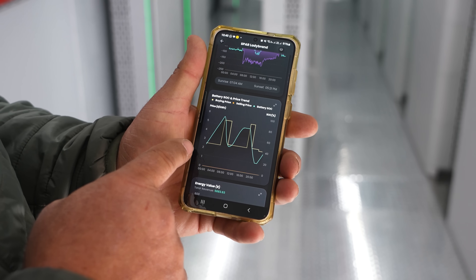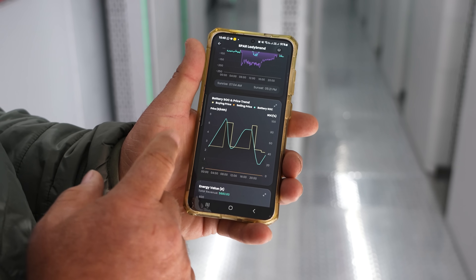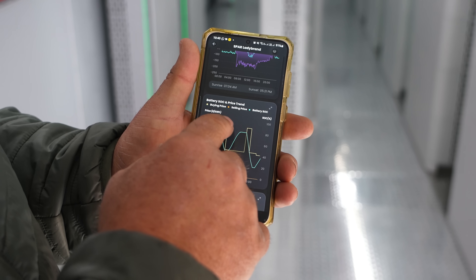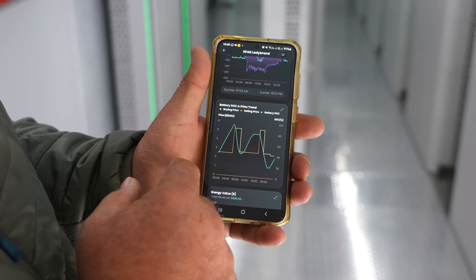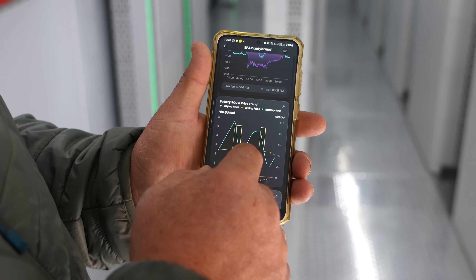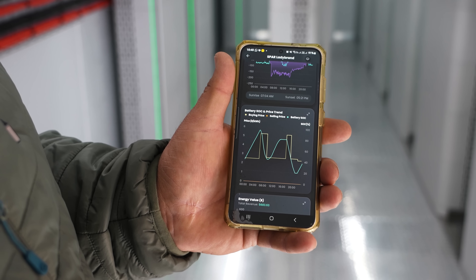What you can see here is the battery state-of-charge profile. We charge the batteries up in winter during the night after 10 o'clock, when the cheapest power price period is. Then when the peak period comes — where power has basically doubled in price — we discharge the battery so we don't draw any power during the peak. There's a peak period in the morning from six to nine and another in the afternoon from five to seven, and as you can see, both those peak periods consume battery power only.